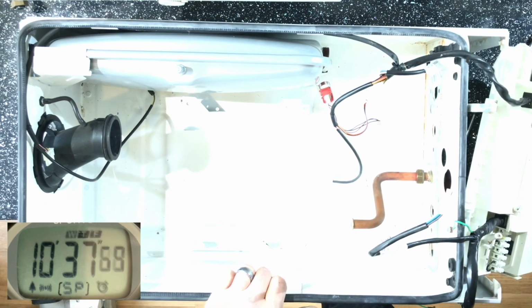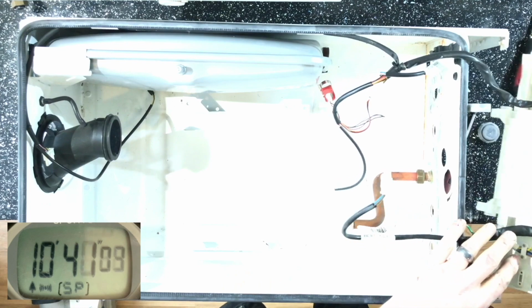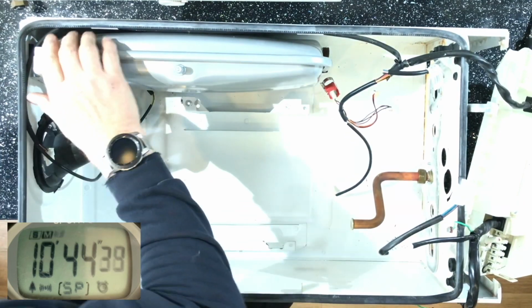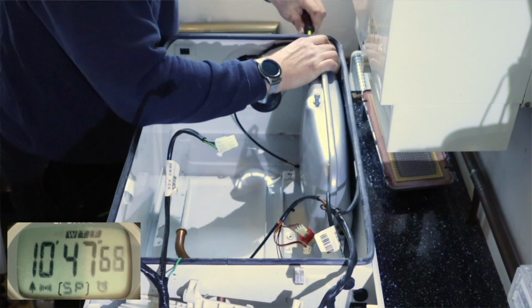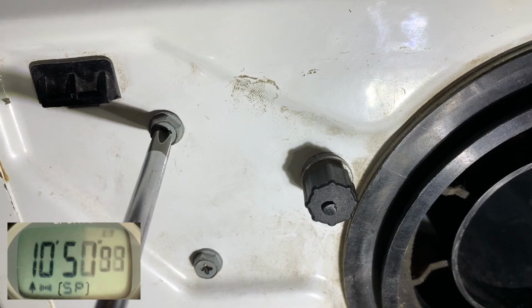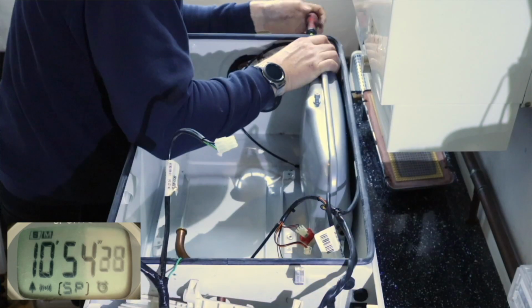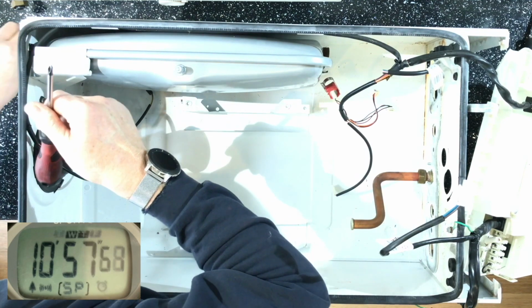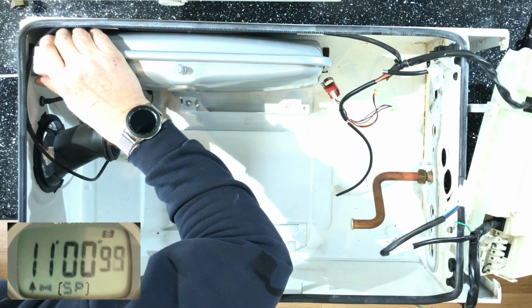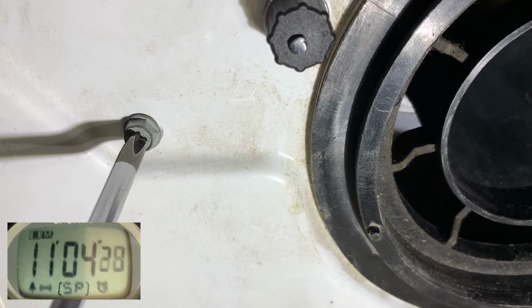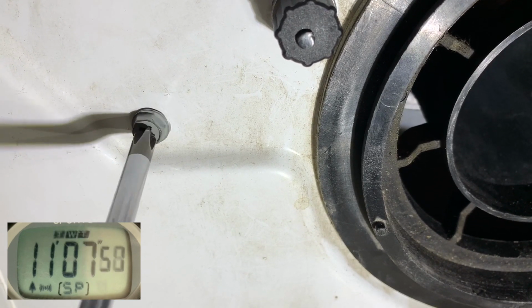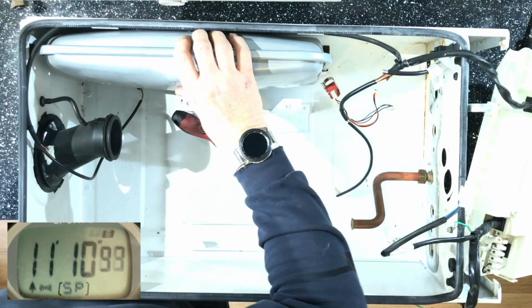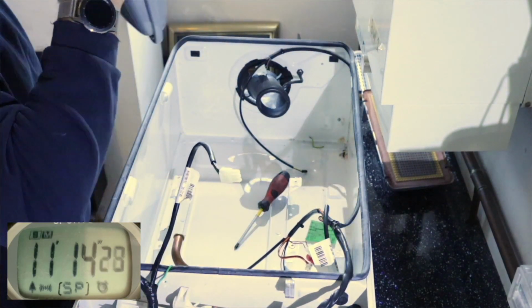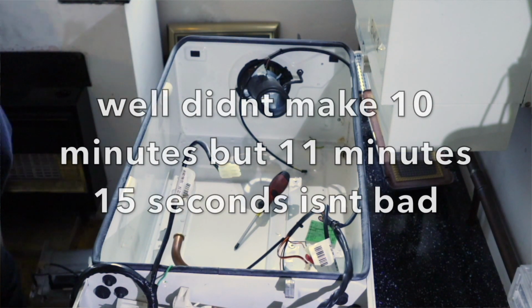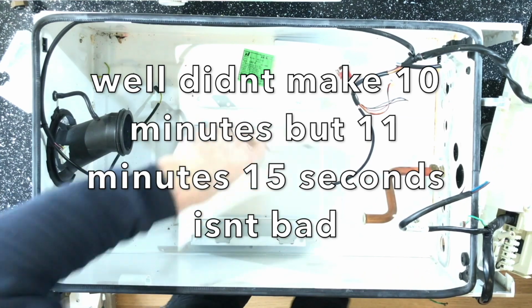And you will be pressurizing them to about 0.75 to 1 bar. So when you're checking them on the service, that's what pressure you should be checking in there, obviously with no pressure in the boiler. And it's literally just held on with these 2 screws, so one at the top, one at the bottom, and a clip, and then it should just slide out. And that's how easy it is to remove this expansion vessel. And so that is all the components taken out of this boiler.